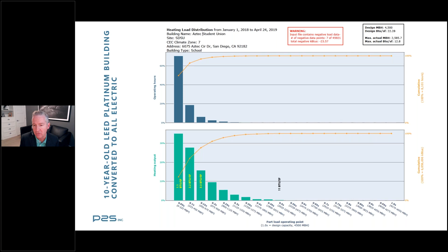And so you have the ability in these types of systems, if you want to go for existing retrofits and you don't want to put in the cost of a full all electric system, to do something different. What we're seeing, at least in the Western United States, is we can put in 20% of the peak on an all electric technology, supplement it with a gas boiler technology that's running at 180 for those peak conditions, and still offset 80% of the carbon emissions that are coming from the gas boilers. And that, from a life cycle cost standpoint, is a good solution when you're looking at retrofit solutions. Next slide, please.